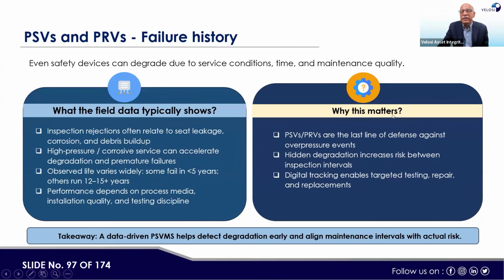So why does this matter? PSVs and PRVs are the last line of defense against overpressure events. Hidden degradation increases risk between inspection intervals. Digital tracking enables targeted testing, repair, and replacement. So takeaways: a data-driven PSVMS, a PSV management system, helps detect degradation early and align maintenance intervals with actual risk.